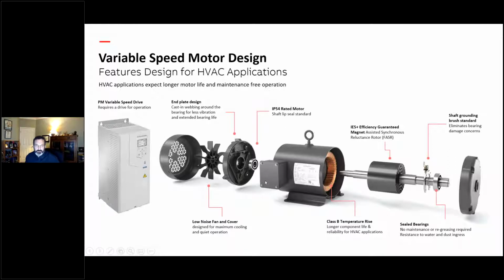IP55 in IEC, IP54 for HVAC applications, just to seal up the motor and provide you a design that you don't have to worry about dust and light condensation that's going to take out the motor. Again, it requires a drive to operate, and because it requires a drive, we recommend having a shaft grounding brush on here or ceramic bearings, and that's basically to deal with electrical discharge. So when you have a drive on a motor, you have capacitive coupled currents and common mode voltages that can cause shaft discharges, and that basically pits away at the bearings and causes premature failure.